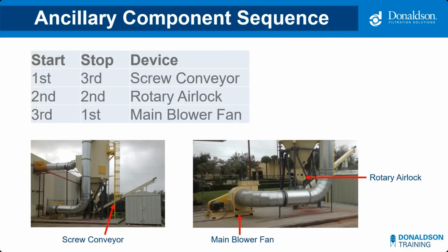So here's an example showing the starting and stopping sequence of a collector system with some ancillary components. Here we have a conveyor, a rotary airlock, and the main blower fan. The key is to start with the device that is furthest away from the main blower fan and start them in sequence with time delays in between. We would start the conveyor first, and then the rotary airlock, and then start the main blower fan last. Shutting the equipment down is in the reverse order of the startup sequence. The main blower fan would be the first to stop, and then the rotary airlock, and finally the screw conveyor.